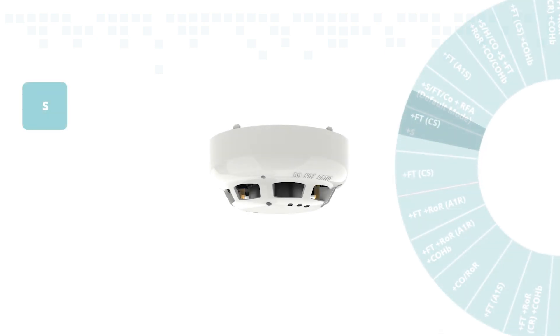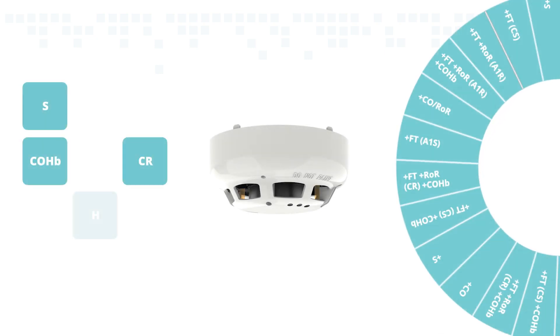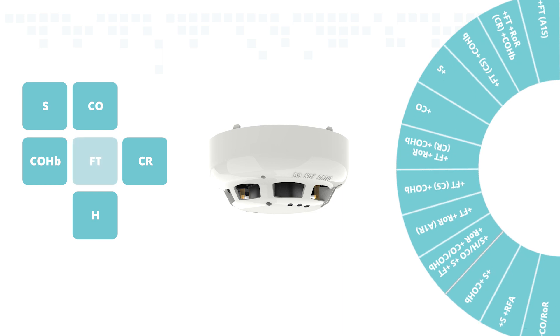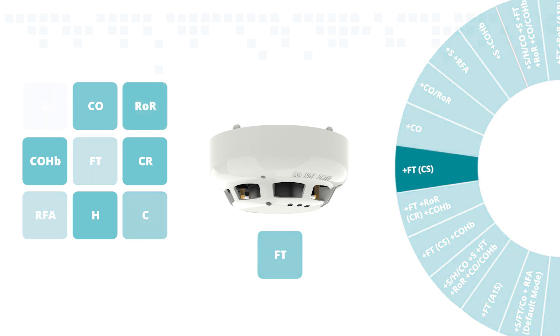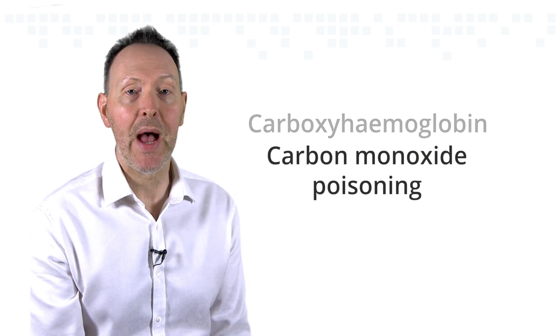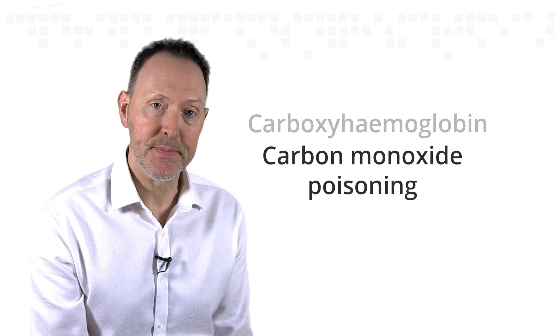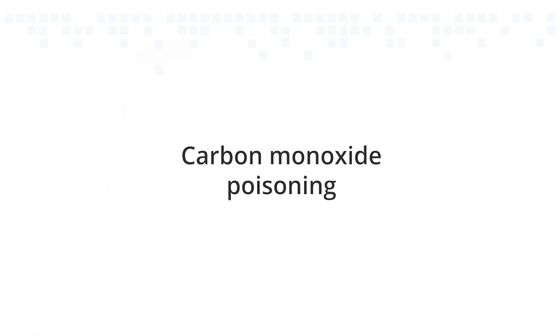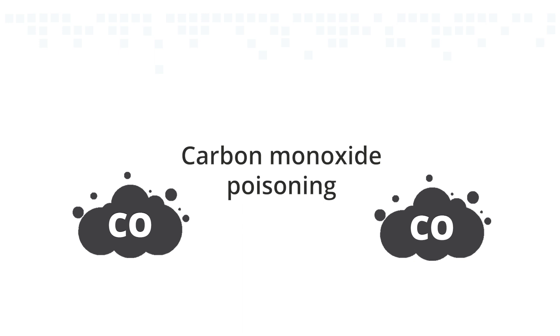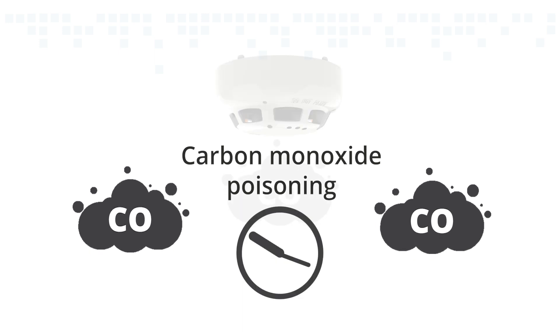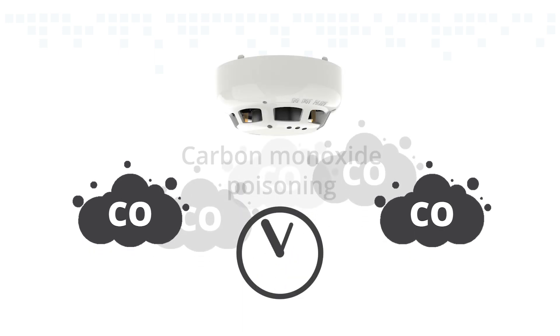The ACD employs several modes where the CO sensing element is used to enhance the sensitivity of the other sensing elements to better detect a real fire over a false alarm. But this sensor can also recognise the threat of carboxyhemoglobin toxic poisoning, commonly referred to as carbon monoxide poisoning. This is usually suffered as the result of either a sudden high exposure to CO or a prolonged exposure over time, so the ACD becomes equipped with modes that monitor for both.